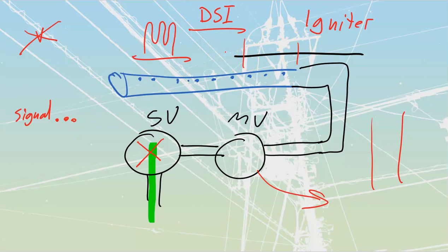Some of them will attempt restrikes. It's very common in a lot of gas-fired appliances that they will do three restrikes. Three strikes and you're out, basically. It'll try, and if it can't ignite, it'll wait a little bit. They won't start up right away. They'll usually run a fan to dissipate any gas so we don't have huge amounts. Then it'll try again, and then it'll wait, and then it'll try again. And if we can't get that thing going, then it's going to shut down.